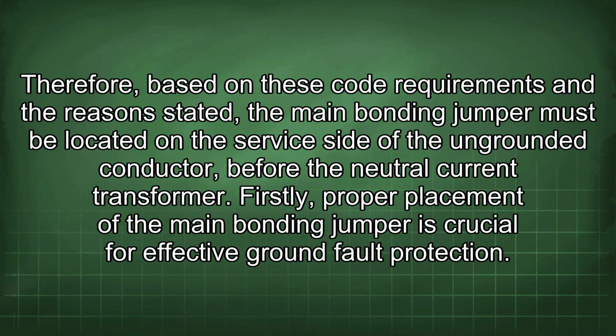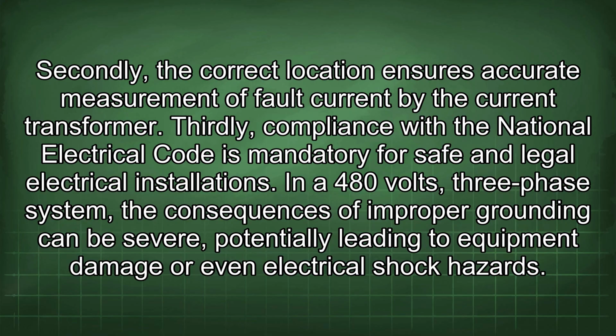Therefore, based on these code requirements and the reasons stated, the main bonding jumper must be located on the service side of the ungrounded conductor before the neutral current transformer. Firstly, proper placement of the main bonding jumper is crucial for effective ground fault protection. Secondly, the correct location ensures accurate measurement of fault current by the current transformer. Thirdly, compliance with the National Electrical Code is mandatory for safe and legal electrical installations.